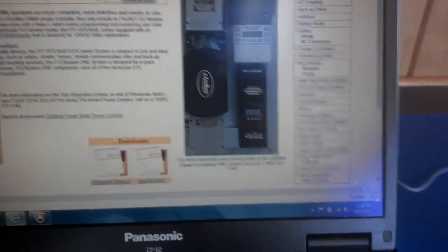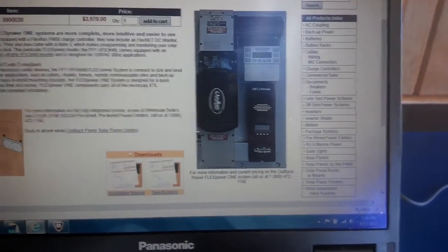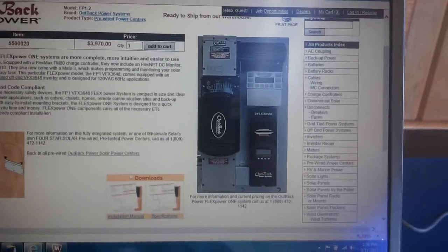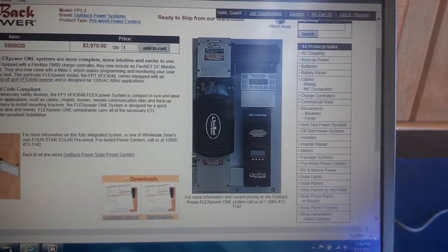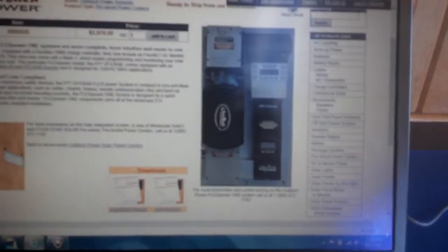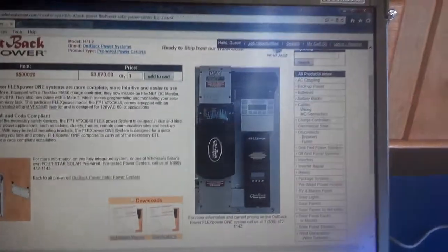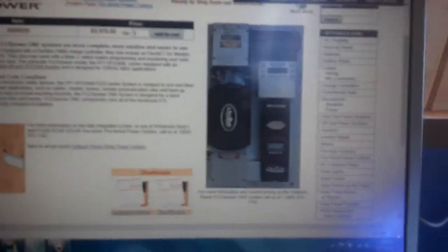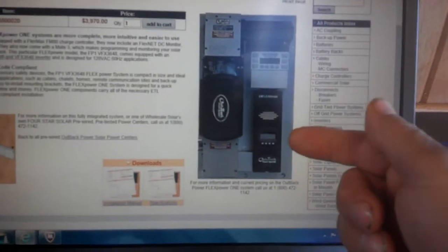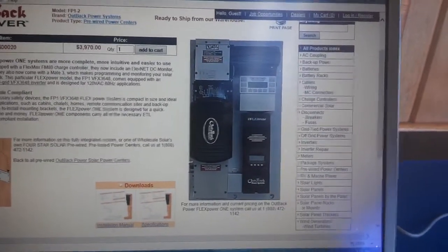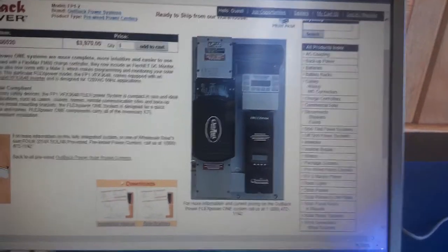They'll be coming into the combiner box and then running. We're hoping to keep this less than 100 feet. I should back up. The reason why we couldn't go with 16 panels is that after 15 panels, we'll have hit the maximum, keeping the safety limits within it to work for the charge controller. So the client will be able to add to the system, but in order to do that, he's going to have to get another charge controller, and at that point he could add panels in multiples of 3. So he could add another 3, another 6, 9, 12, you get the idea.